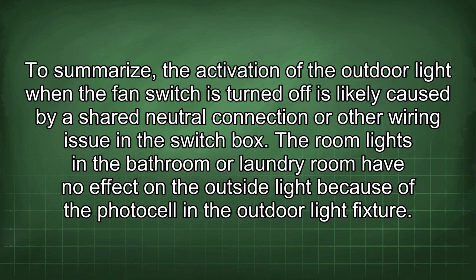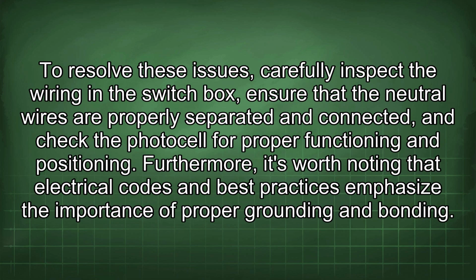To summarize, the activation of the outdoor light when the fan switch is turned off is likely caused by a shared neutral connection or other wiring issue in the switch box. The room lights in the bathroom or laundry room have no effect on the outside light because of the photocell in the outdoor light fixture. To resolve these issues, carefully inspect the wiring in the switch box, ensure that the neutral wires are properly separated and connected, and check the photocell for proper functioning and positioning.